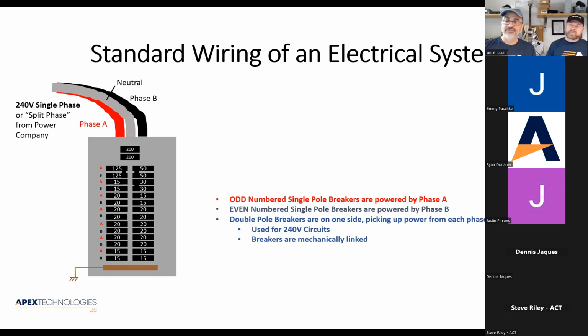That means that those two are physically linked together. And if one of those breakers should trip, it's going to automatically trip the other breaker, because if you have a 240 volt oven that has two hot lines going to it, if one of them is to trip, the other one you want to go ahead and disconnect as well. So that's the telltale sign, if they're connected together, that it's probably a 240 volt load.